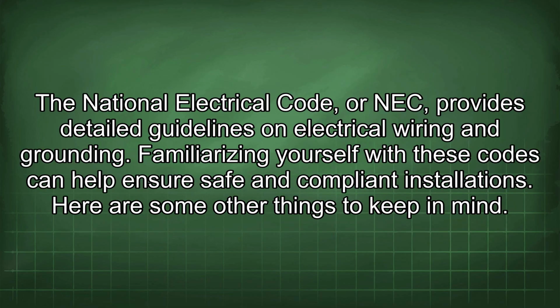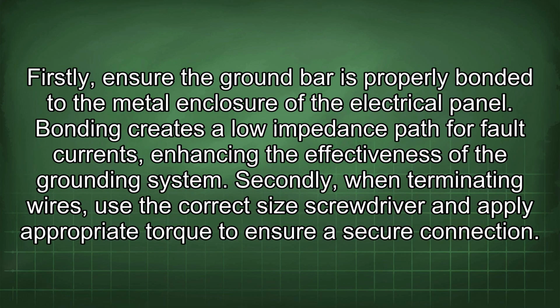The National Electrical Code, or NEC, provides detailed guidelines on electrical wiring and grounding. Familiarizing yourself with these codes can help ensure safe and compliant installations. Here are some other things to keep in mind. Firstly, ensure the ground bar is properly bonded to the metal enclosure of the electrical panel. Bonding creates a low impedance path for fault currents, enhancing the effectiveness of the grounding system.